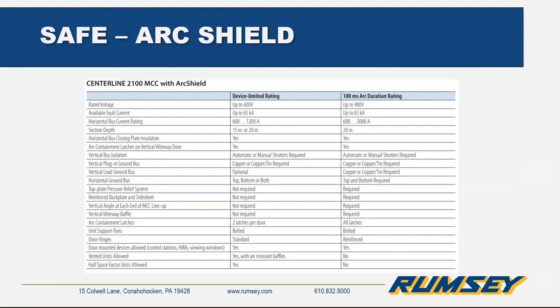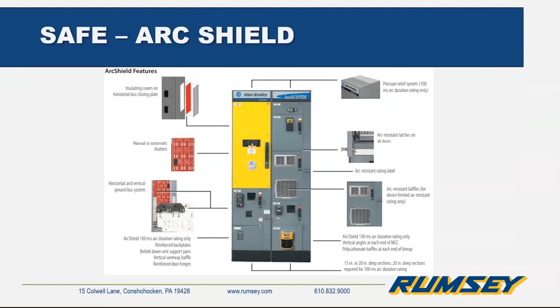This slide here actually shows some of the features of ArcShield and where exactly they're located. So there's the pressure relief system on the top that I just mentioned. There's also arc-resistant door latches, which allow pressure and heat to safely escape the enclosure without any parts or doors being blown off. You can also see there's a baffle on the middle unit on the right section. And then there's even an arc-resistant label that they put right there on the MCC nameplate, which is located on the vertical wireway cover. And you can't see them here because their doors are all on, but there's also, again, your manual and automatic shutters and your steel barriers and things like that.